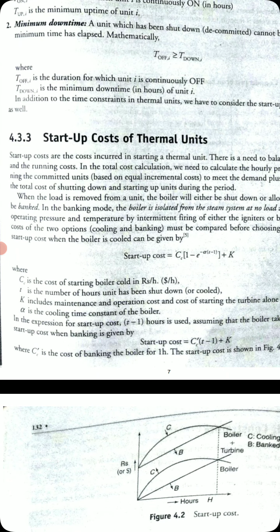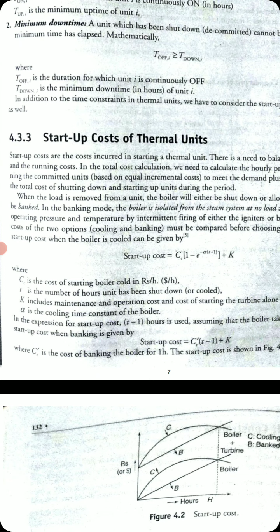The expression for startup cost uses T minus 1 hour, assuming that the boiler takes 1 hour to start up. The startup cost of banking is given by CT dash into (T minus 1) plus K, where CT dash is the cost of banking the boiler for 1 hour. So we will see one graph.